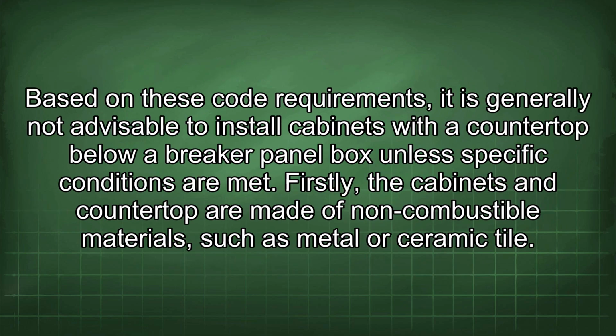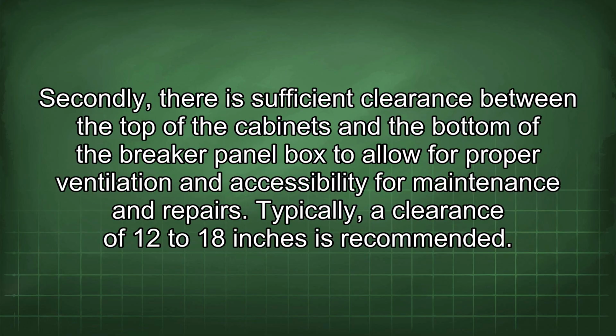Based on these code requirements, it is generally not advisable to install cabinets with a countertop below a breaker panel box unless specific conditions are met. Firstly, the cabinets and countertop are made of non-combustible materials such as metal or ceramic tile. Secondly, there is sufficient clearance between the top of the cabinets and the bottom of the breaker panel box to allow for proper ventilation and accessibility for maintenance and repairs. Typically, a clearance of 12 to 18 inches is recommended.